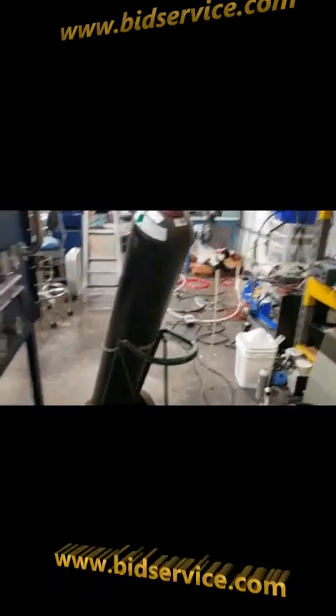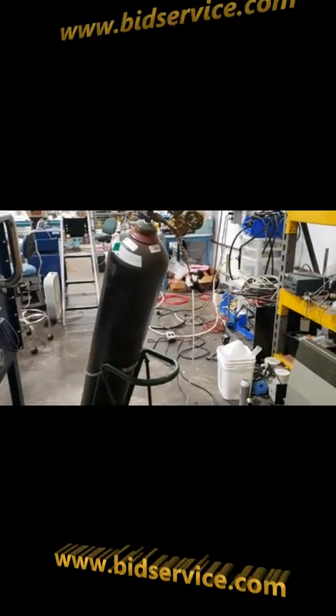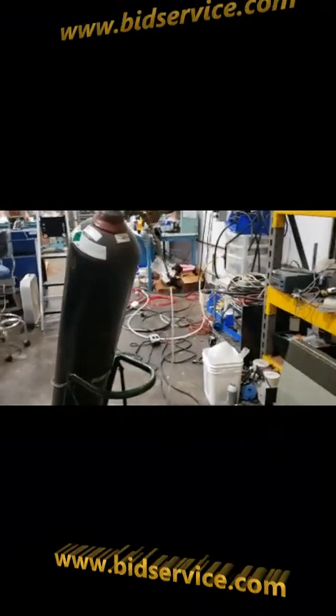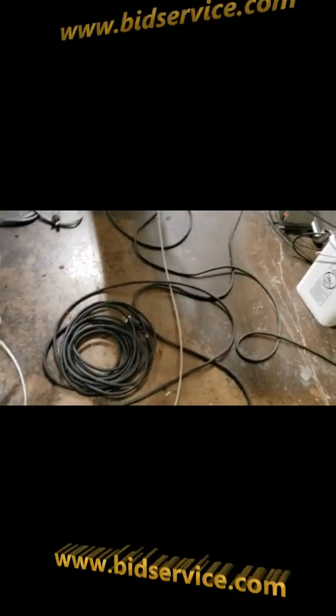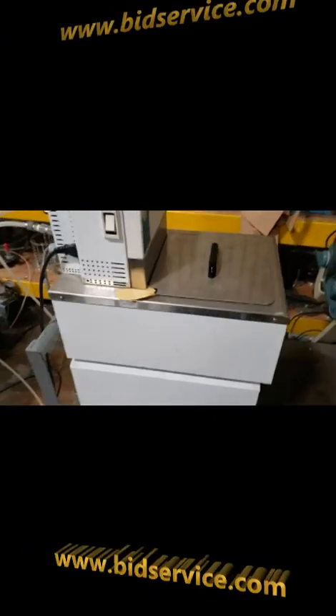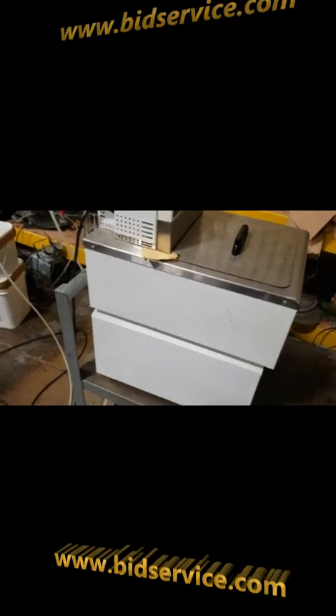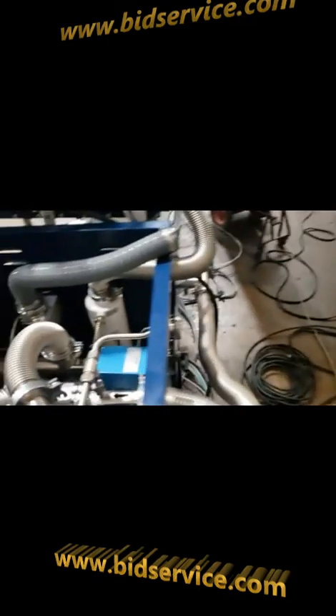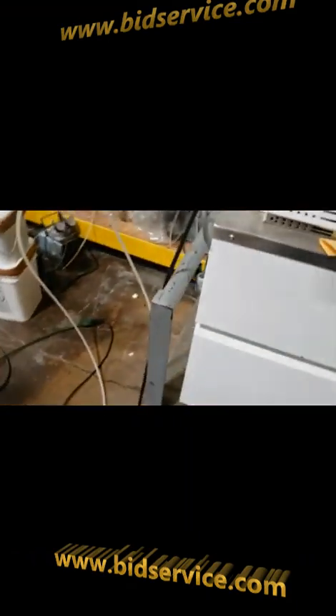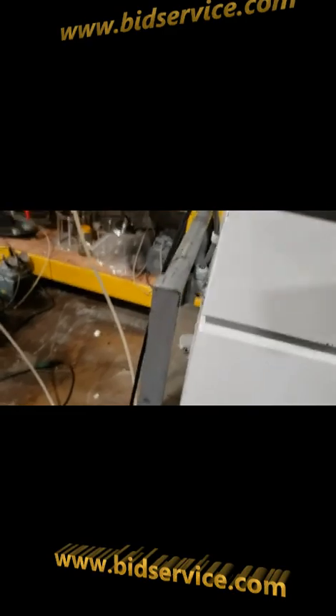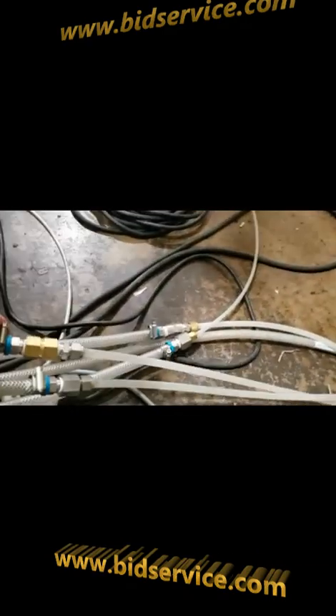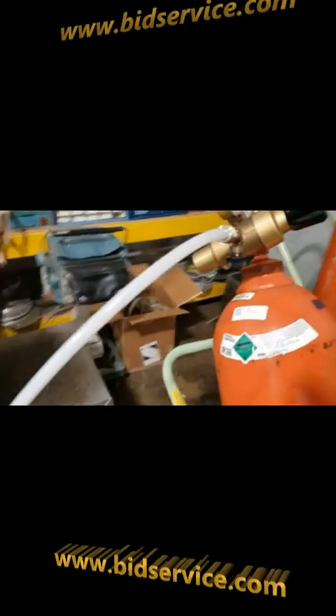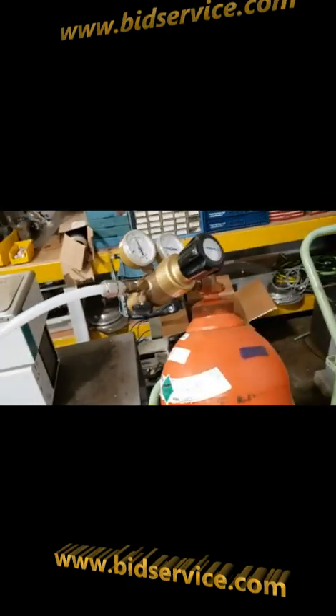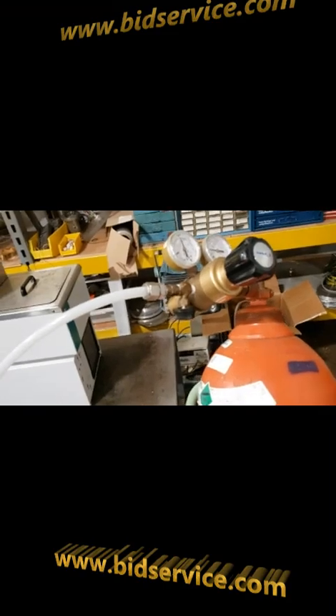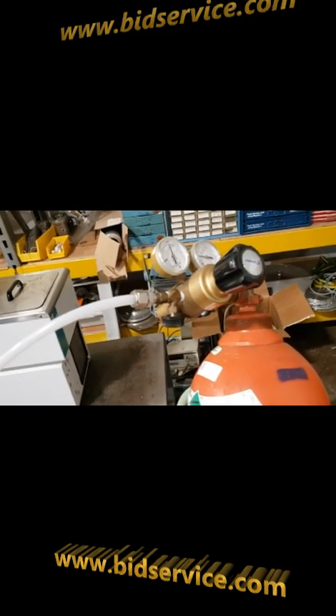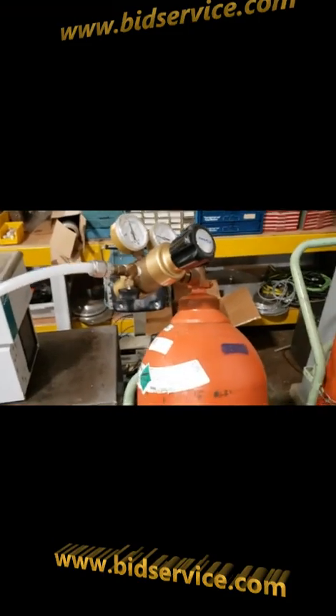So as you can see, here's our regeneration tank. You'll have to supply your own regulator and tanks, and your line leading up to your 1/4 inch fitting. I'm using a house chiller here. If you want to, go ahead and use the heat exchanger. You'll have to run your own cooling water into it. Again, that's through your 3/8 inch lines here. And then I have our inert gas tank here and regulator. You'll have to supply your own. Again, this is our house regulator. And we're using nitrogen in this case.